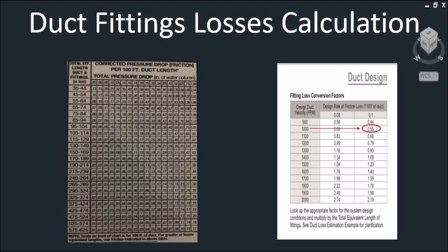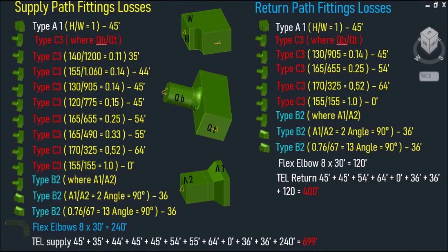As you can see, this is a corrected pressure drop chart which tells us what the pressure losses are through our fittings. And this is a fitting loss conversion factors chart, which allows us to convert the total equivalent length of our fittings for our system design. Since our main duct velocity design is 1000 FPM, as you can see it is reading 0.55.